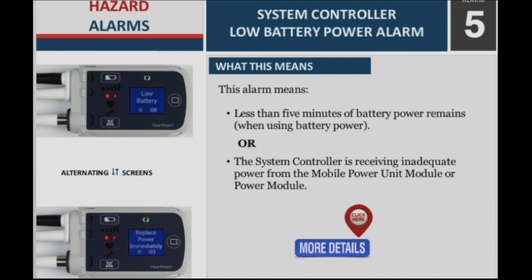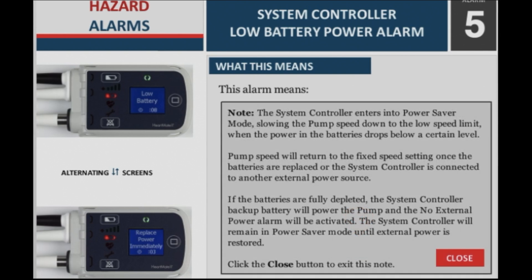The system controller enters into power saver mode, slowing the pump speed down to the low speed limit, when the power in the batteries drops below a certain level. Pump speed will return to the fixed speed setting once the batteries are replaced or the system controller is connected to another external power source. If the batteries are fully depleted, the system controller backup battery will power the pump and the no external power alarm will be activated. The system controller will remain in power saver mode until external power is restored.